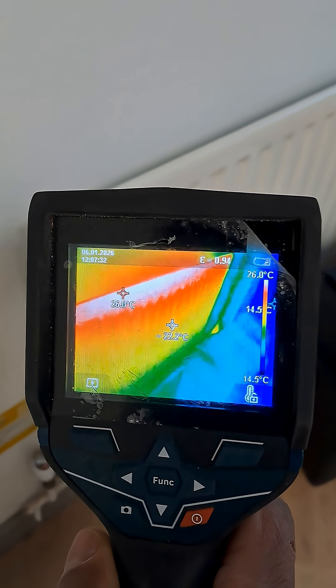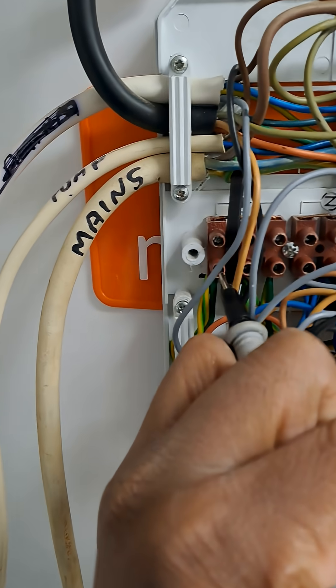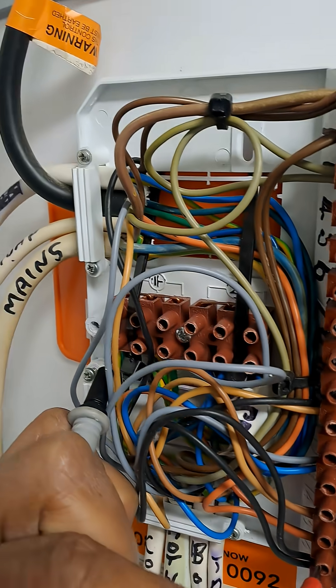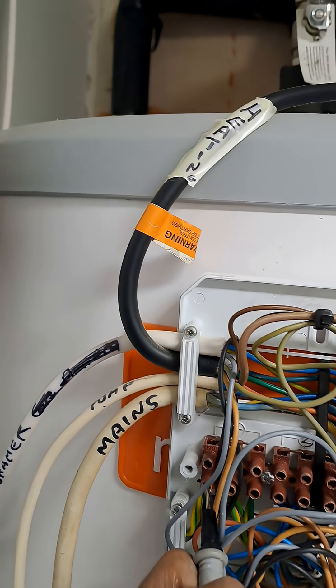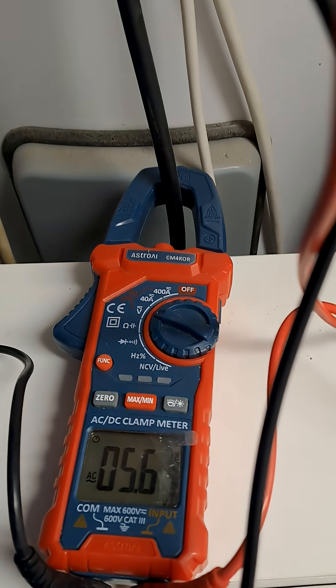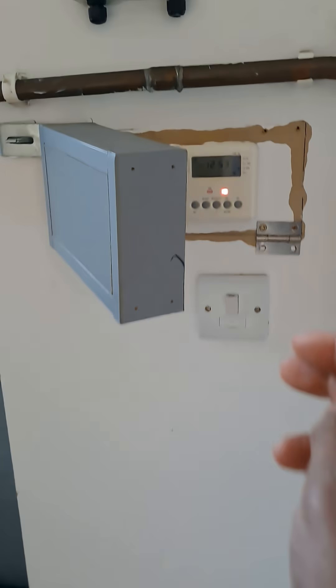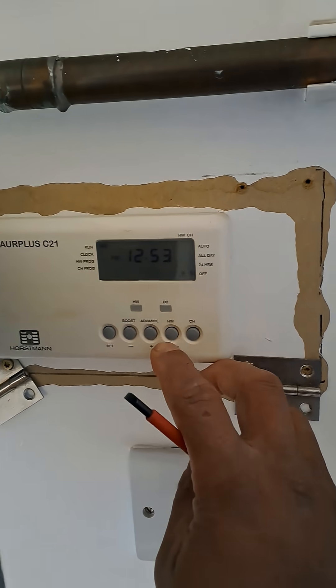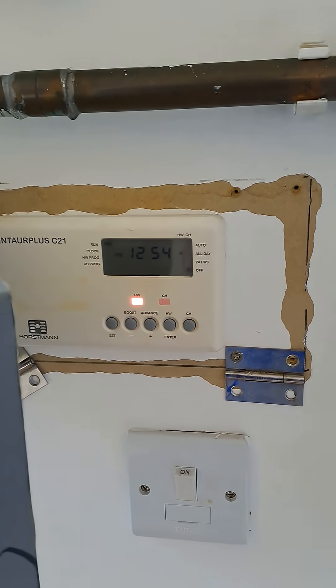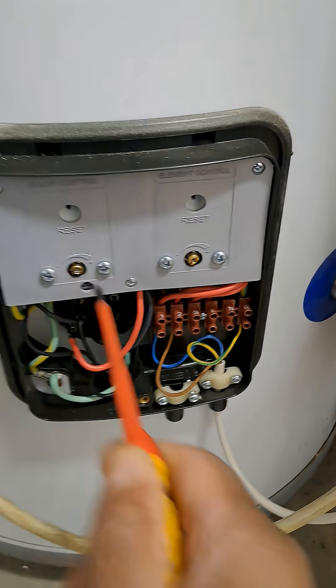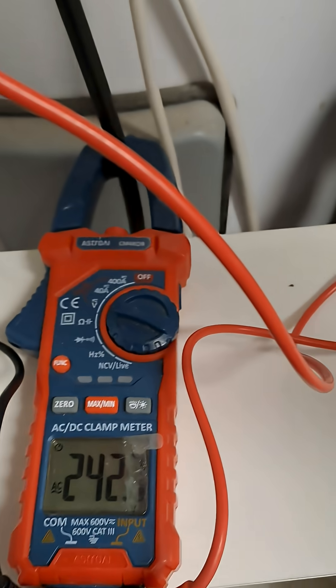This is the radiator that's slightly hot, but that's from previous times. I'm checking the switch live, so I've put a demand on the programmer for heating. There is no room thermostat, so this is against building regs. I'm checking the switch live because it should have 230-240 volts to it, and it didn't — so that's telling me there's potentially a problem with the actuator.